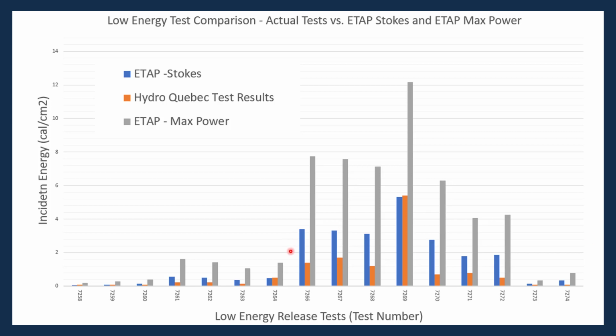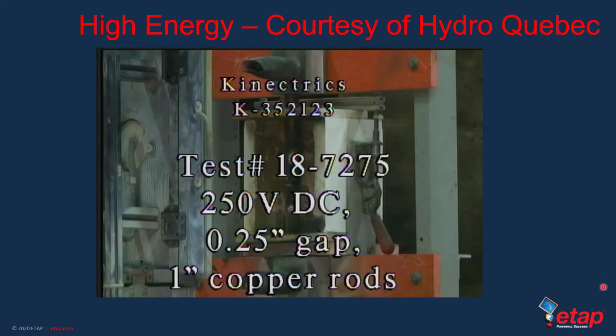So our ETAP result is conservative, yet not overly conservative, by a factor of 6 times. This is what we can conclude from this particular test with 8,000 amps of DC short circuit current available. Now let's look at another video where we can see a different condition.